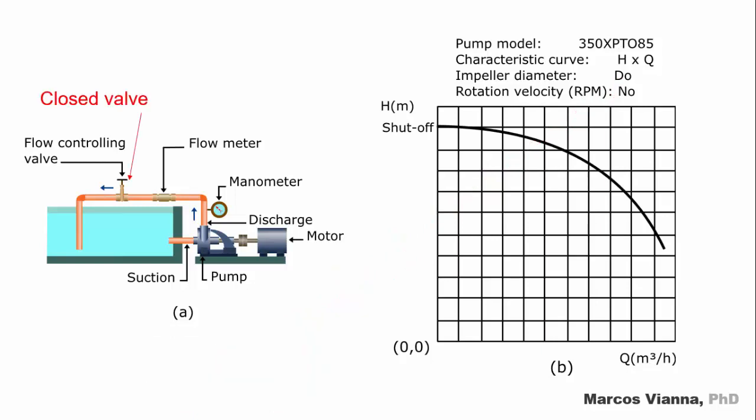Let us start the test with the flow controlling valve completely closed. The flow in the system will be zero and the pressure indicated at the discharge of the pump will be maximum. We call it shutoff pressure.